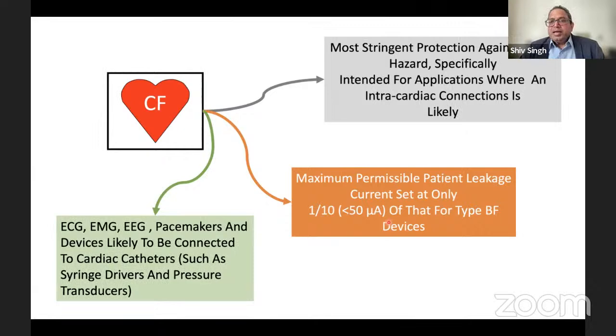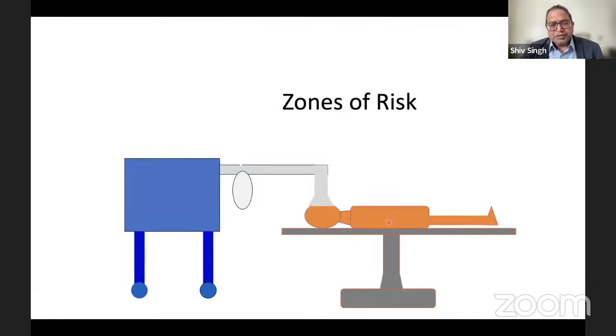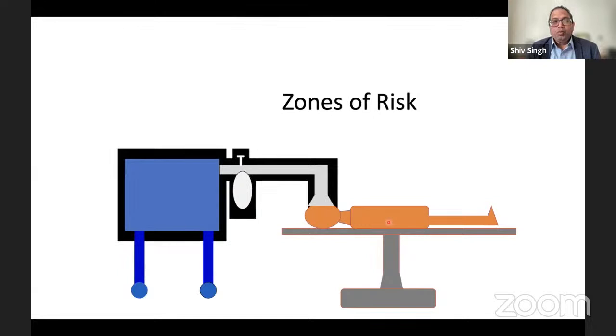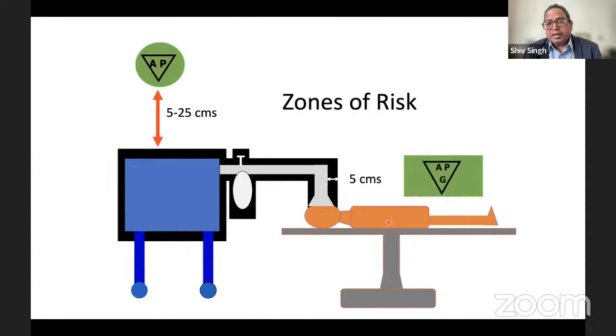Next comes the classification which is about flammability. Zones of risk are around the patient, within 5 centimeters. This is enriched with oxygen, which supports combustion, and also nitrous oxide, which we don't use as much now, but if it is there, it supports combustion. So that's the enriched environment within the 5 centimeters. But if you go beyond 5 centimeters, to 25 centimeters, the gases are going to get diluted with air. So any equipment which is beyond 25 centimeters or within 5 to 25 centimeters can be anesthetic proof. But if it is within 5 centimeters, it needs to be anesthetic proof G. G stands for gases.